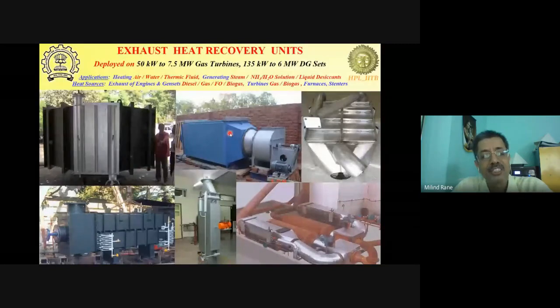Going to the other side now, many of our gensets and turbines or your furnaces are exhausting heat at a fairly high temperature. And if we can recover that heat and use it for generating steam, or for regenerating liquid desiccant, or for heating up air or thermic fluid, we can use it for various processes. So we have deployed various technologies. These are all based on our patent. In fact, my first patent when I came back to India in 1993 from the US was on a hybrid matrix heat recovery unit.